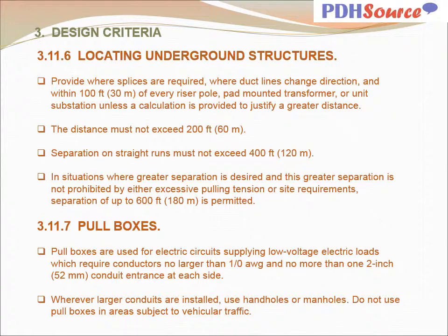In situations where greater separation is desired and this greater separation is not prohibited by either excessive pulling tension or site requirements, separation of up to 600 feet is permitted.